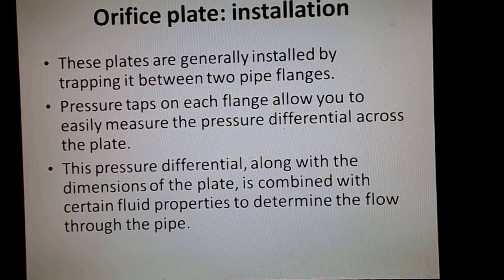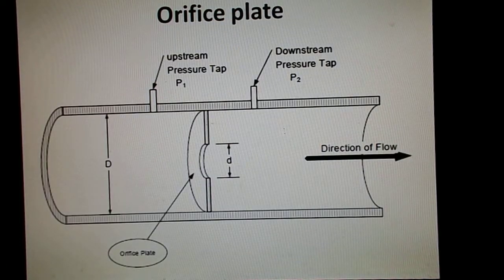and the pipe flanges are designed such that we have pressure tappings across the pipe flanges, and they are measuring the downstream pressure and upstream pressure across the orifice plate, and thus we obtain differential pressure P1 minus P2, which determines the flow rate.